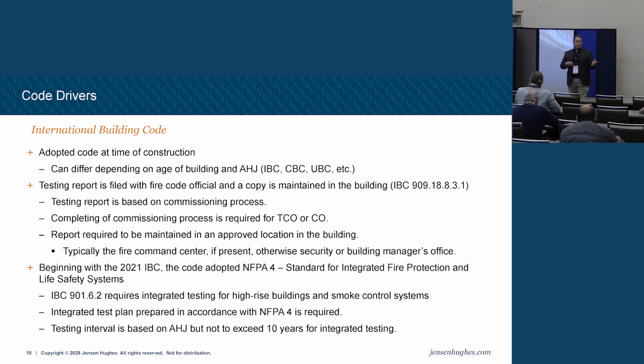So I said earlier, how do you know if you have one of these systems? You should have documentation on it, and it should be a pretty clear thing. There should be a test report showing it was tested. If you have smoke control designed into the building, you have to have that system fully tested and commissioned before you can get a TCO or CO, or occupancy. And the report is required to be maintained in the fire control room or the fire command center.